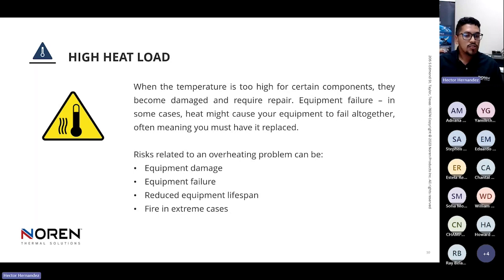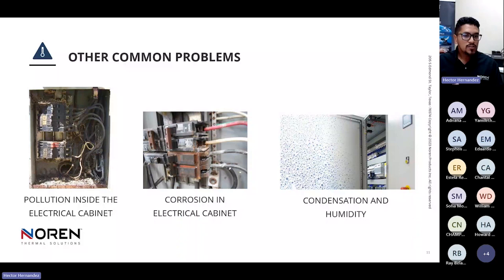The most used technology for its low cost is the two fans technology: one fan that is introducing the air and one fan that is exhausting this air. But the problem with this technology is that we introduce the ambient air. This ambient air can have dust and moisture. This dust will enter the electrical panel, even if we adapt a filter to it, because filters are not capable of trapping 100% of particles. So these particles will enter the electrical panel and form a thin layer of dust. This thin layer of dust will prevent the heat transfer from the equipment to the air. Thus, we can have overheating even if we have airflow, because the air is not in contact with the equipment, it's in contact with the dust, and the dust is not a heat conductor.